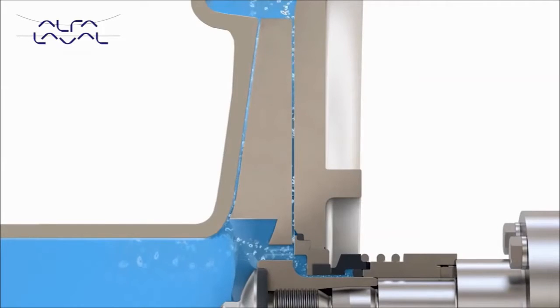Balancing holes also allow equalization of pressure between front and back of the impeller. This reduces shaft and bearing loading, increasing pump and motor life, lowering maintenance cost.